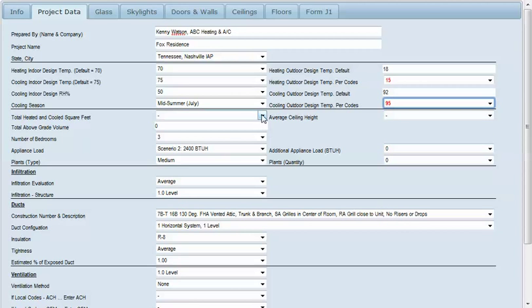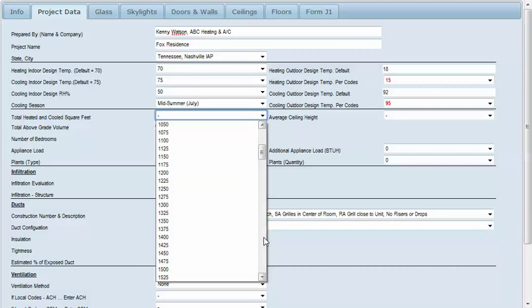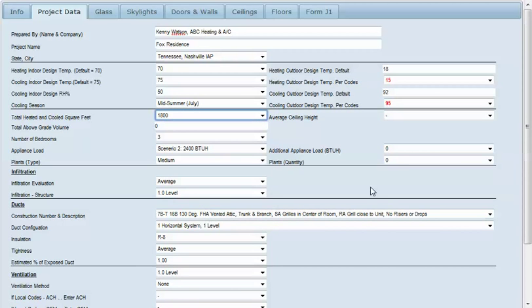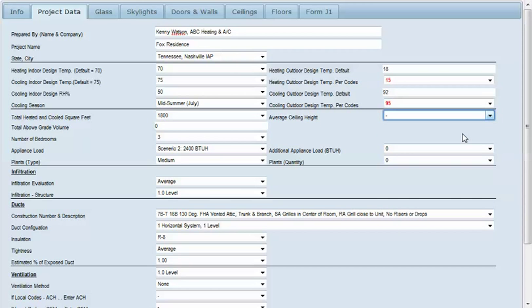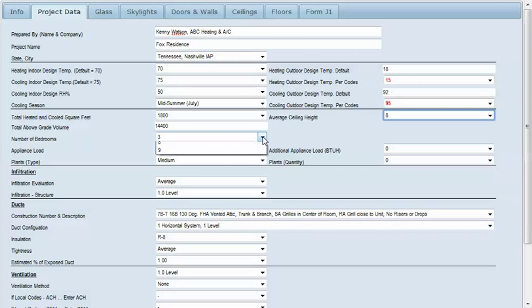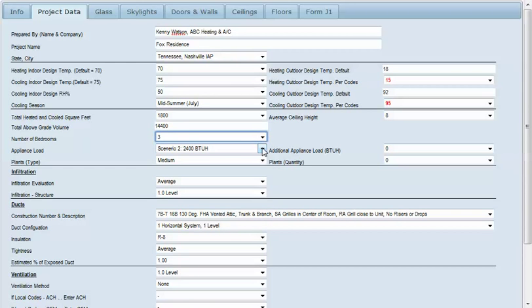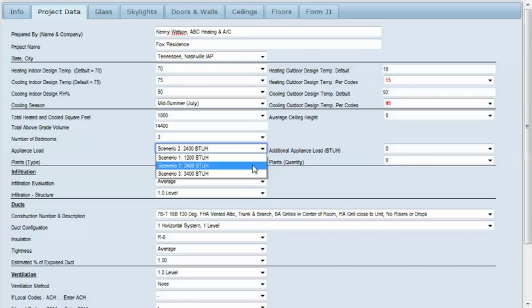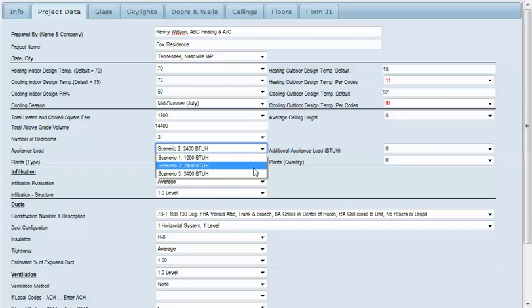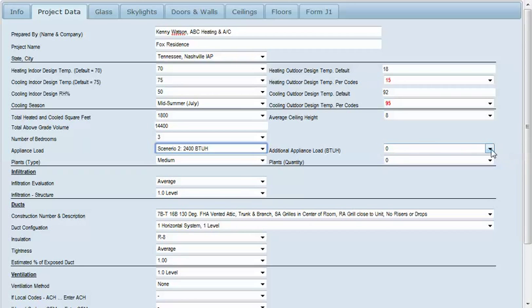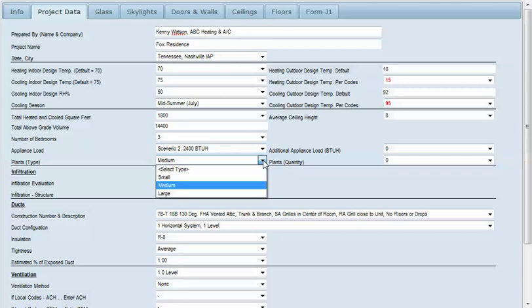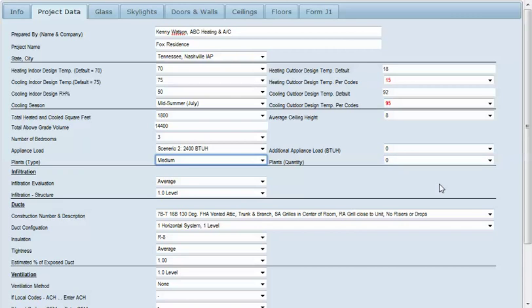Our home today has a total of 1800 square feet and we have an average ceiling height of eight feet. That will calculate our total above grade volume of 14,400. This is a three bedroom house. You have three appliance scenarios: 1200, 2400 and 3400. This home is suitable for the 2400 BTU scenario. You can also add some additional appliances here if you need to. We're going to leave the plants blank, but you would select large, medium or small and the quantity.